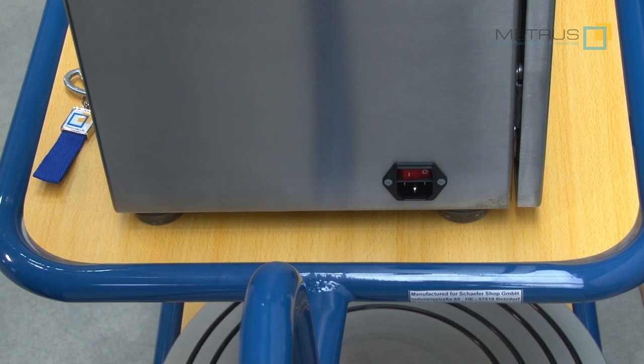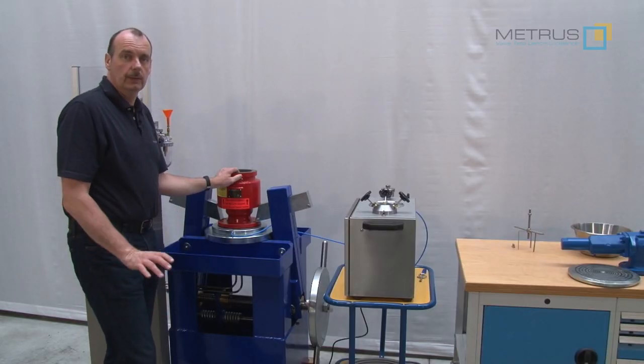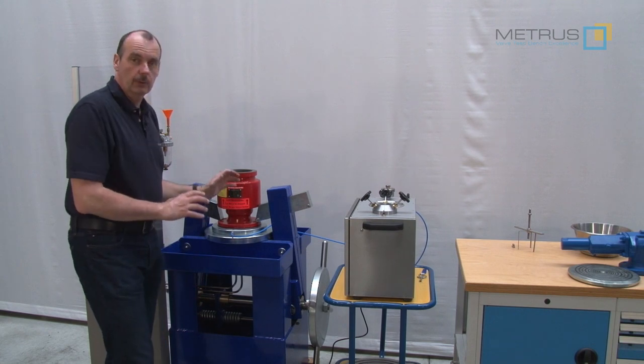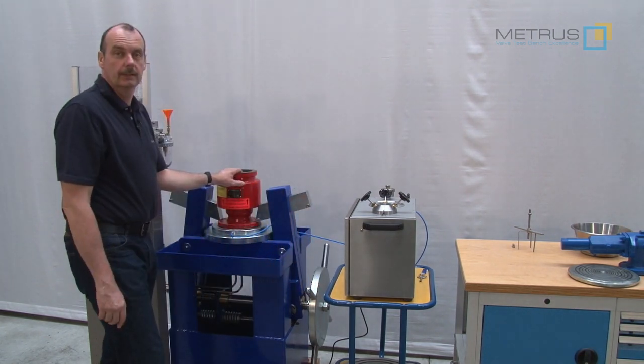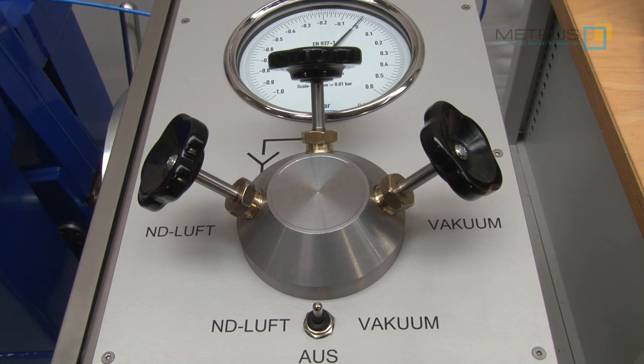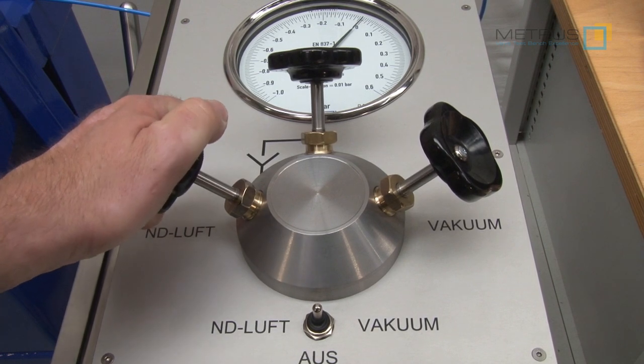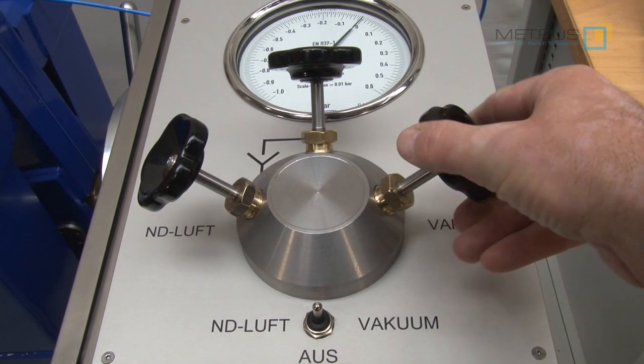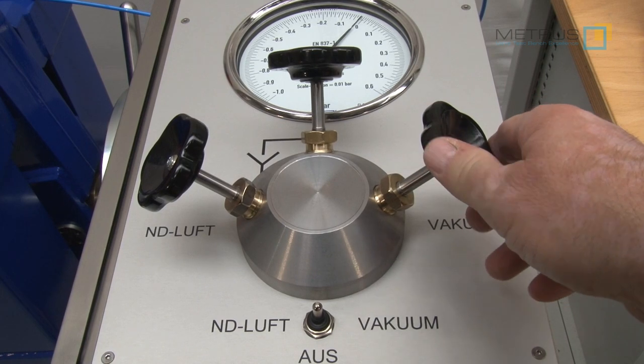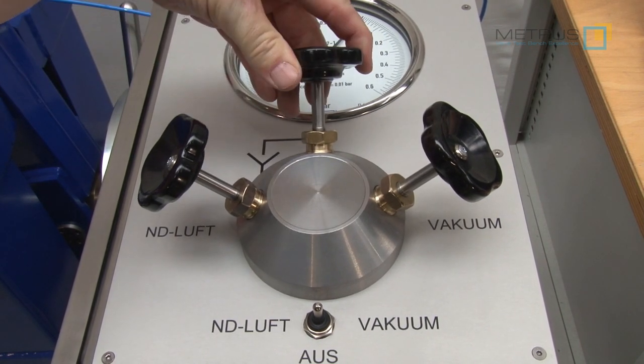To operate the vacuum tester we need to connect it to a power supply and switch the main power on. We don't need a very high force to clamp the valve onto the sealing plate, so we just clamp it very smoothly and this will be sufficient. On the Metrus vacuum tester we are using a valve head with three needle valves: one for the low pressure compressor up to 0.5 bar positive, a second for the vacuum test down to a maximum of minus 0.8 bar, and the third needle valve to release the vacuum or overpressure.